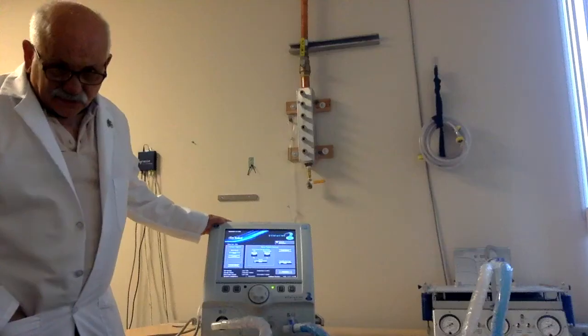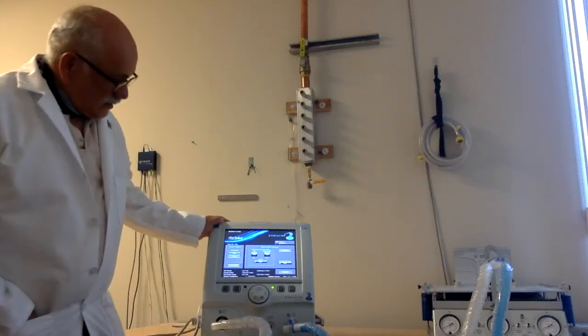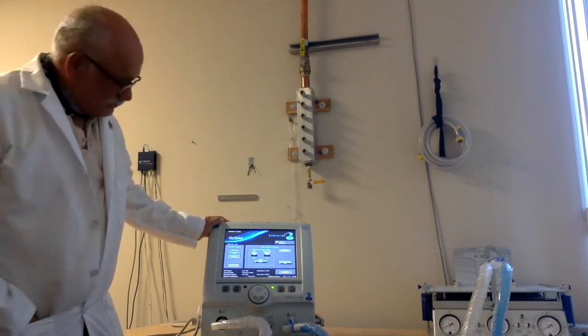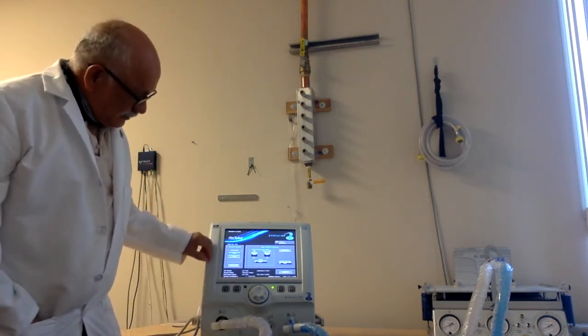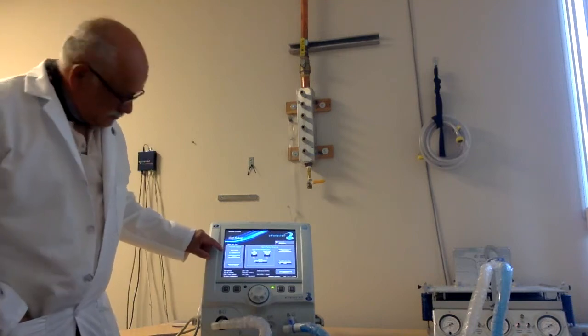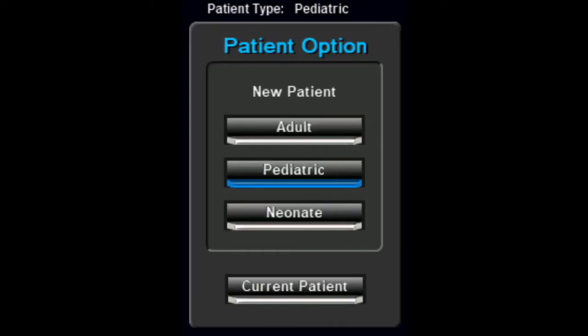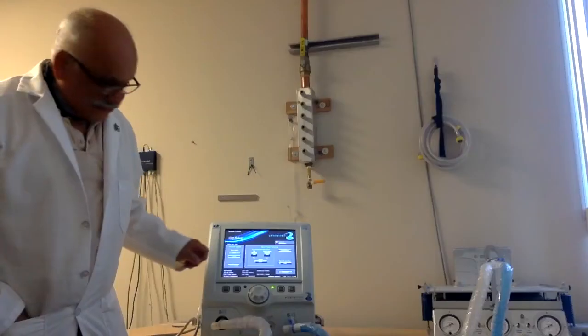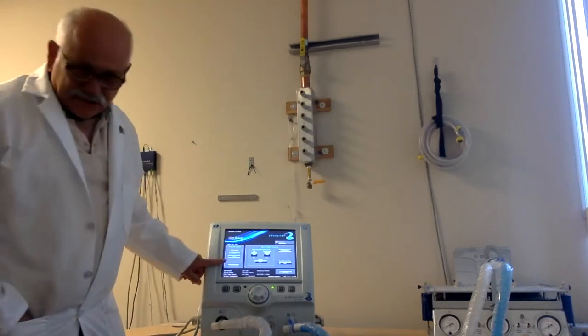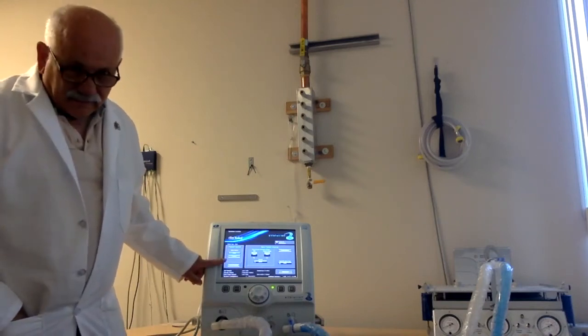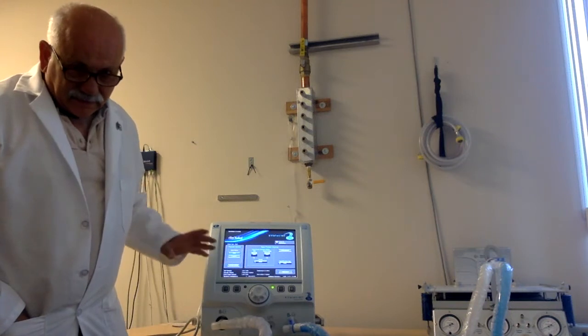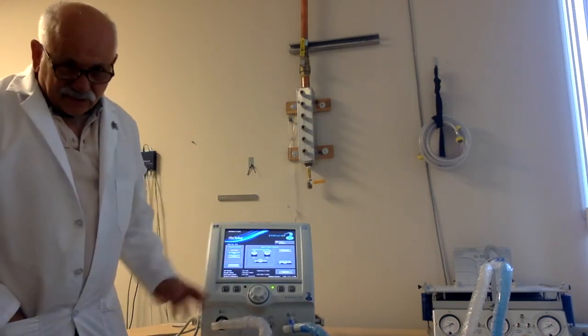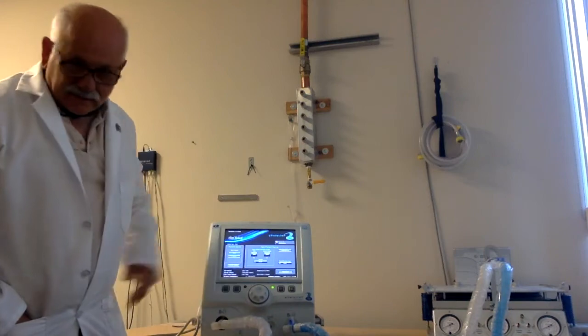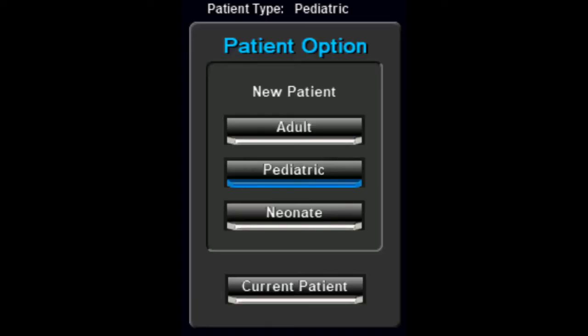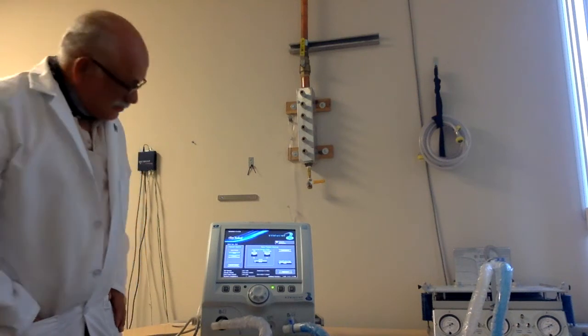So the ventilator has gone through its power-on self-test, and now we're ready to get started. On the left, the ventilator allows you to choose between adult, pediatric, and infant patients. It also allows you, if you were ventilating a patient, took the patient off the ventilator, went to the operating room or to CAT scan, to return and hit current patient. There are also some other methods that you can use to quickly resume ventilation.